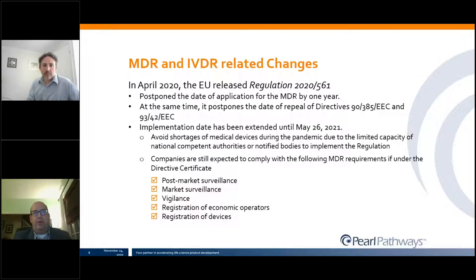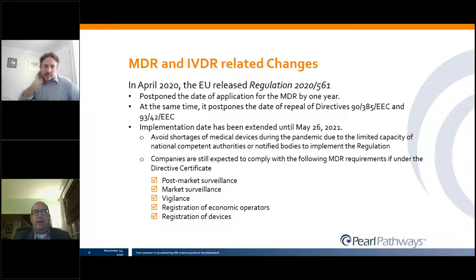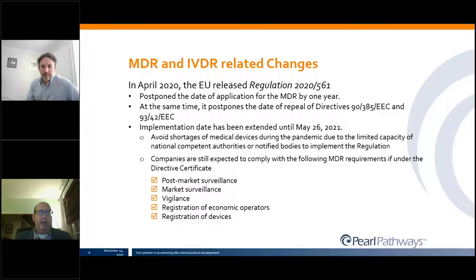It is important to note that companies are still expected to comply with MDR requirements even if their product is still under a directive certificate. That includes post-market surveillance, vigilance, registration of economic operators, and registration of devices. All of that still applies even if you are operating under a medical device directive certificate.